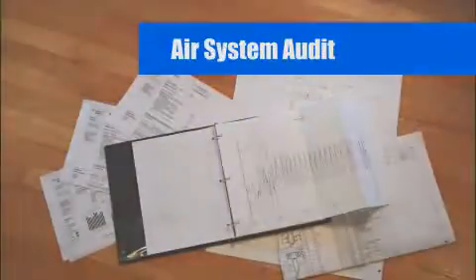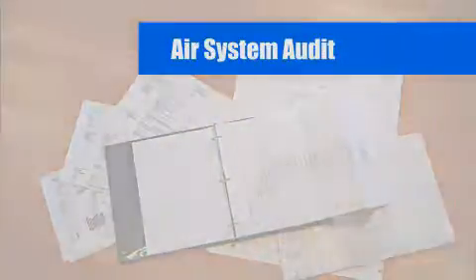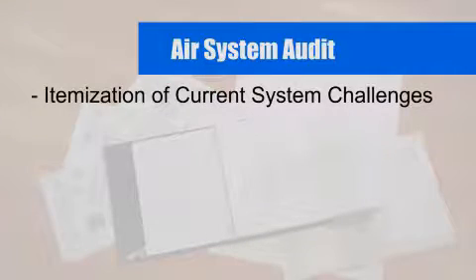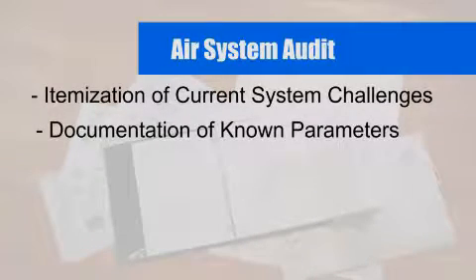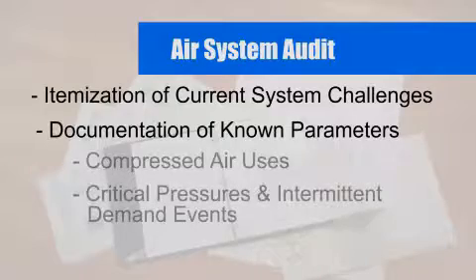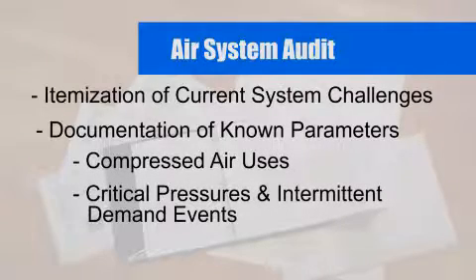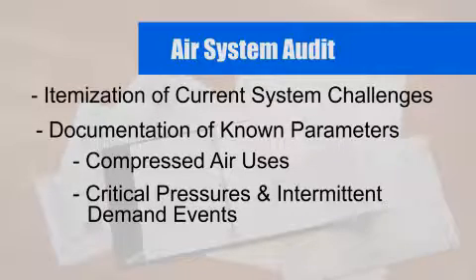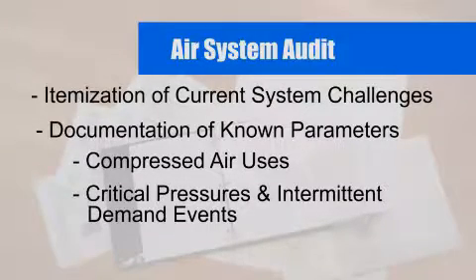The air system audit includes the itemization of challenges, documentation of known parameters including compressed air uses, critical pressures, and intermittent demand events. This is followed by data collection, which includes installation of the monitoring equipment, recorder setup, and data retrieval.